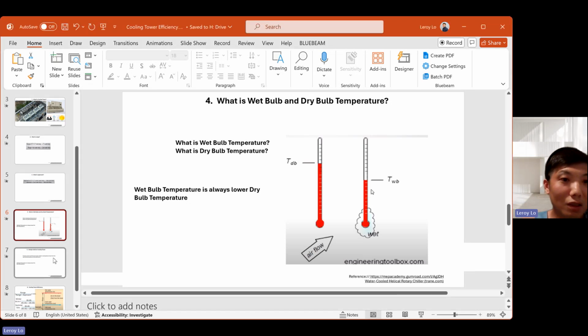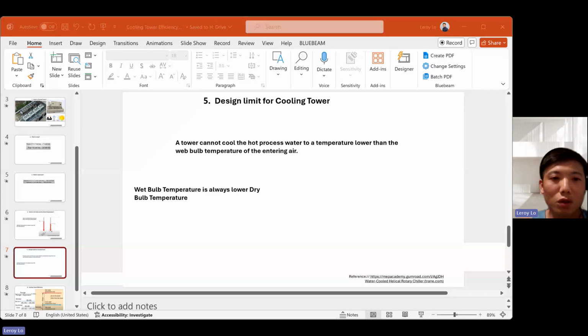Moving on to the next slide. The design limit for the cooling towers. This is the rule here: a cooling tower cannot cool the hot process water to a temperature lower than the wet bulb temperature of the entering air. Basically, it is impossible to cool hot process water lower than the wet bulb temperature of the entering air, because it is impossible to reject the heat to the atmosphere. For example, you have 90-degree water coming in, you want 85 degrees going out of the cooling tower, and your wet bulb temperature is 85. So you can only cool down to 85. If you want to cool to 84, but your wet bulb is 85, then it's impossible.